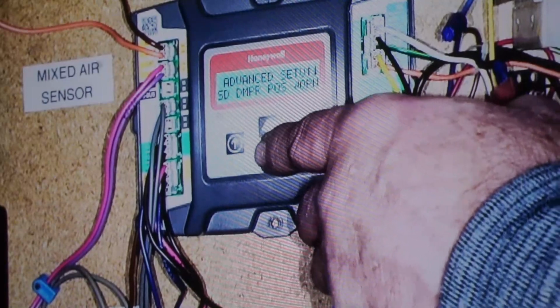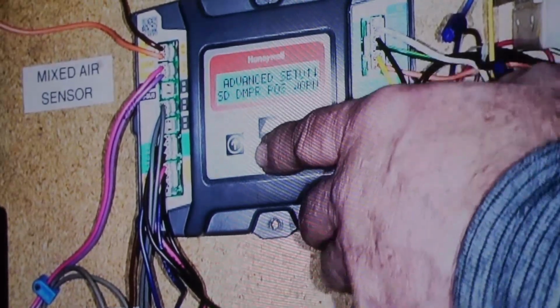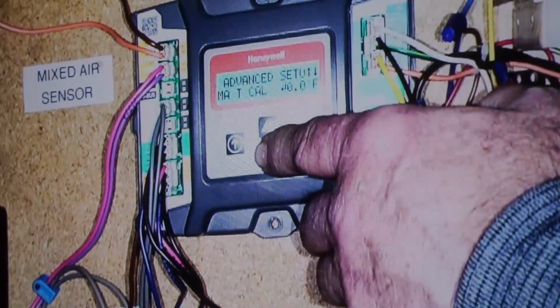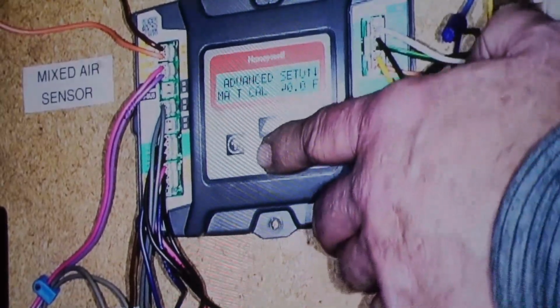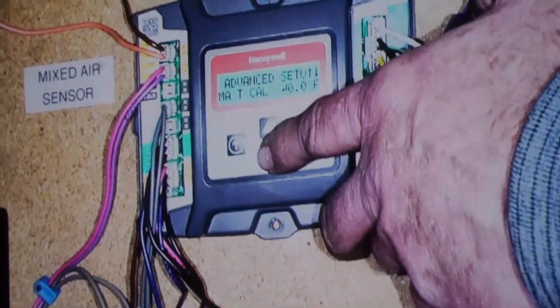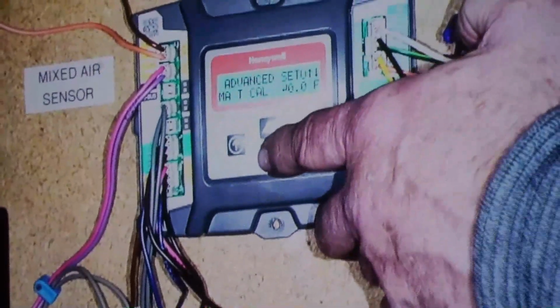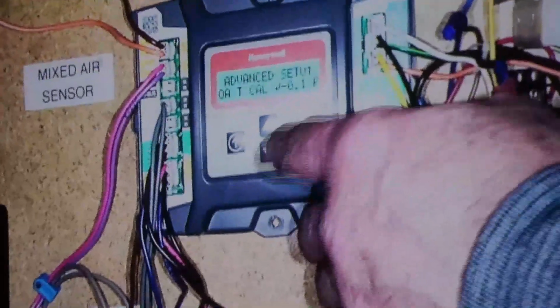Smoke damper we typically don't deal with, but if there is a smoke purge, we can purge it here. And then we can do offsets on our temperature. So we can calibrate. If we think we've got a sensor that's a degree or two off, we can calibrate those sensors right here. And that's the end of that menu.